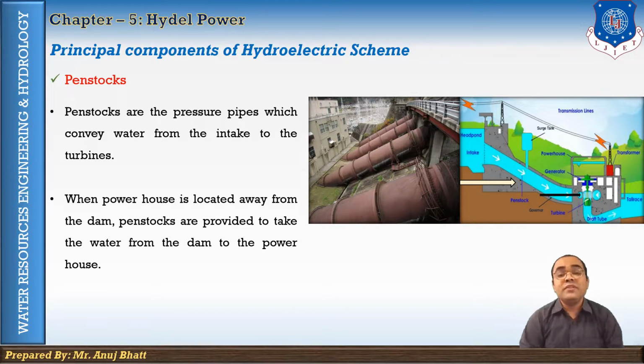Well, when the distance between the forebay and the powerhouse is relatively short, a separate penstock is provided for each turbine. However, if the distance is long, a single large penstock can be provided to feed 2 to 3 turbines. Generally, these penstocks are designed as high pressure pipes. Various materials can be used for the fabrication, such as steel, RCC or asbestos cement, etc.